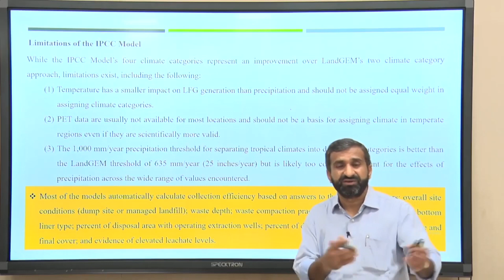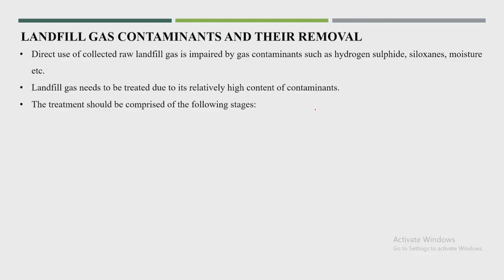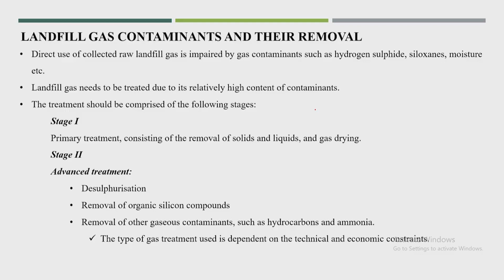Now, landfill gas contaminations and their removal. Direct use of collected landfill gas is impaired by gas contamination such as hydrogen sulfide, siloxanes and moisture. Landfill gas needs to be treated due to its relatively high content of contaminants, and the treatment has stage 1 and stage 2. The primary treatment considers removal of solids, liquid and gas drying, that is the major one, and stage 2 is desulfurization or organic silicon compounds removal.